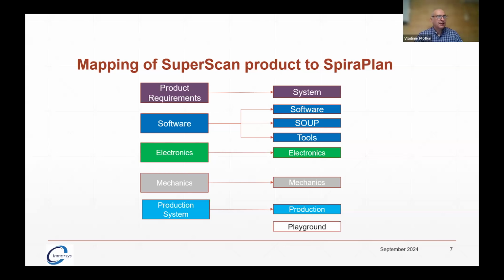And then we'll also have the SOUP level requirements, because as you know, for the medical industry, for IEC 62304, you need to do your SOUP testing. And SOUP is basically software which wasn't invented here. So software is of a known provenance, of a known pedigree. In FDA speak, it's called COTS, commercially off the shelf. Sometimes it's not really commercial, sometimes it's something you take off GitHub, and it's freeware, open source. But generally, it's not something you developed within the 62304 standard.